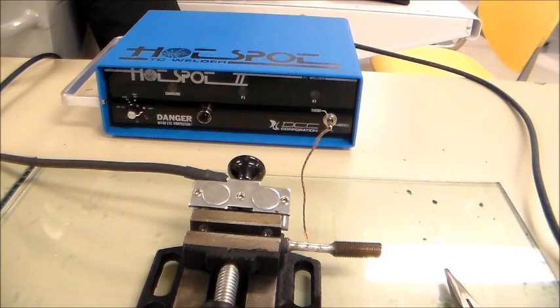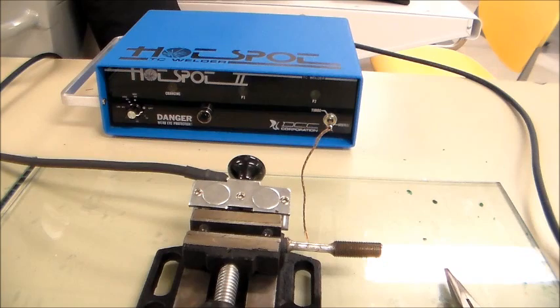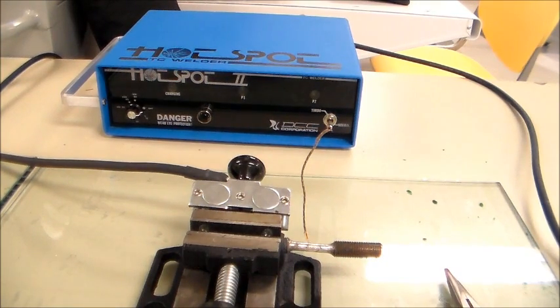This is how the weld thermocouple will look like. Once you are done welding your thermocouple, turn off the welder by rotating the power knob to the off position. Disconnect the welder from electricity and do not forget to clean your working area.